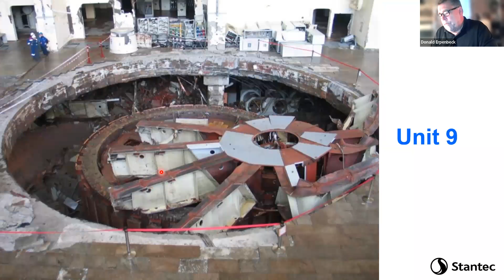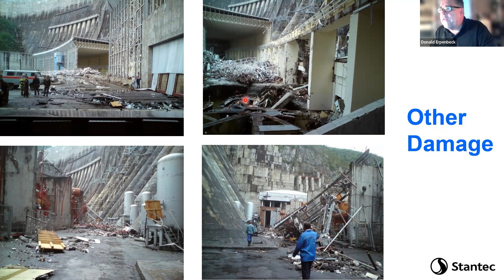Unit 8 looks decent. Unit 9, here the stub shaft completely is gone. The upper bearing bracket completely shifted off. And again, the stator is completely gone and the copper is gone on the rotor poles. Unit 10, right? Some other pictures, just to give you a feel. Here's sort of the transformer area and that area between the powerhouse and the dam where, you know, probably a lot of the shorting out occurred when the water started to shoot through the roof. Parts of the tail race deck, the unit.